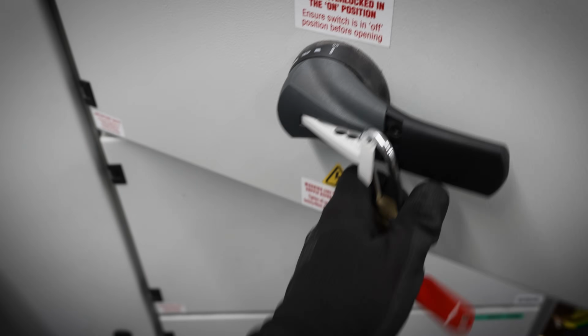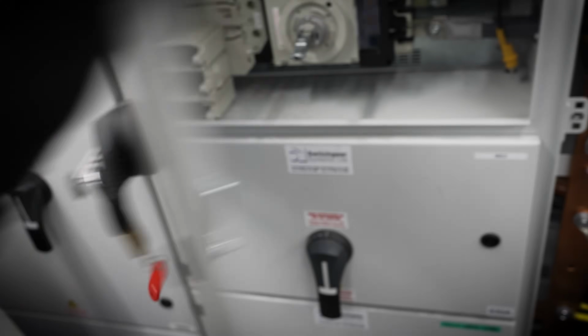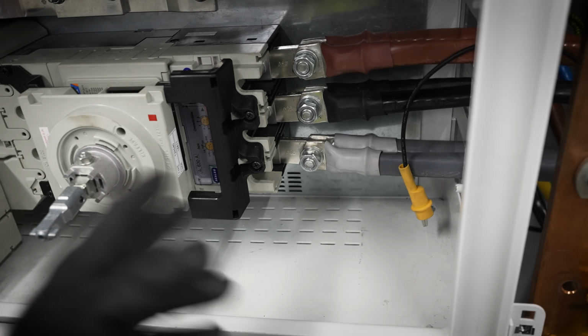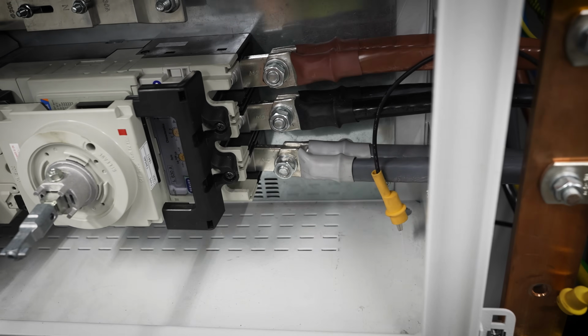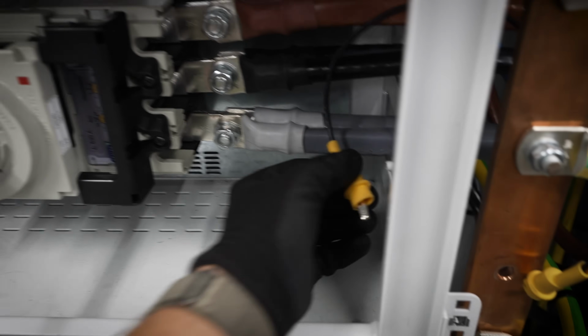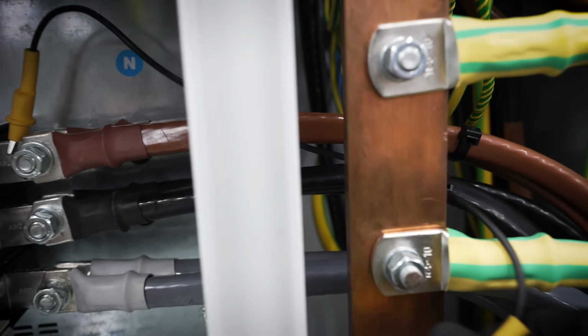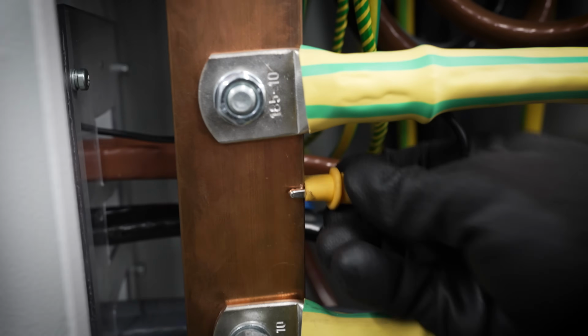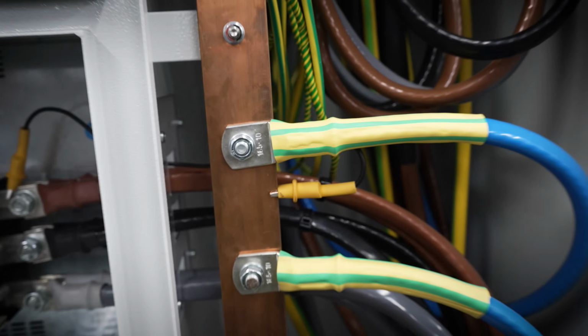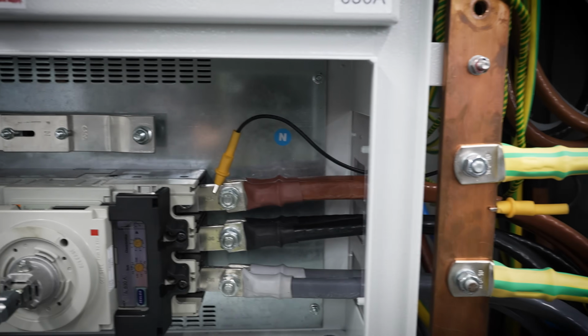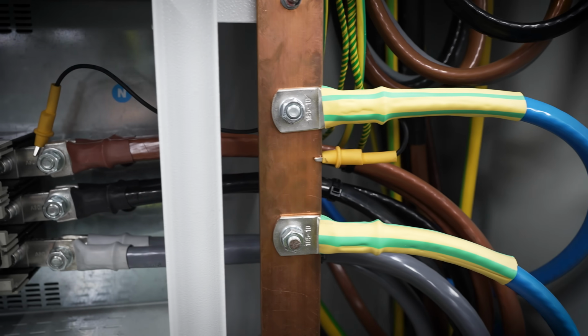Panel's still locked off, so no one can kill me whilst we're doing this. I've proven this dead. It's off anyway. I know the switch works, but it's always good practice. So now I'm just going to bang a link between here and here. Grab this croc clip, put it on there. Grab this one, put it on there. So that is L1 linked out to Earth. So now we can go back upstairs and get our first R1, R2.